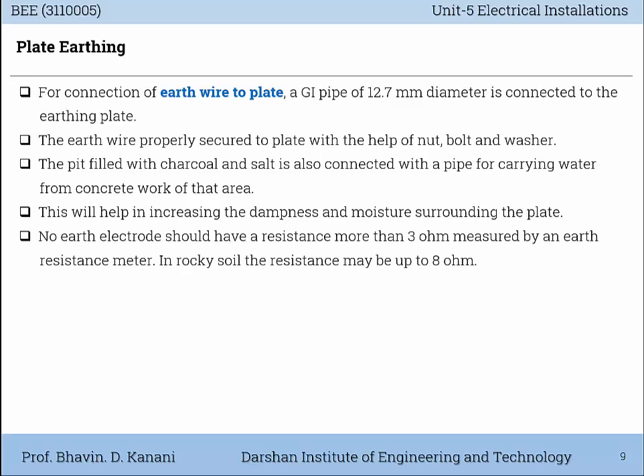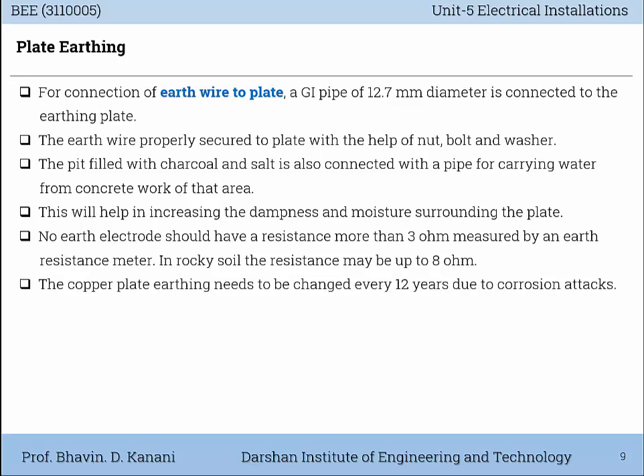No Earth electrode should have a resistance of more than 3 ohms, measured by an Earth resistance meter. In rocky soil, the resistance may be up to 8 ohms. The copper plate Earthing needs to be changed every 12 years due to corrosion attacks.